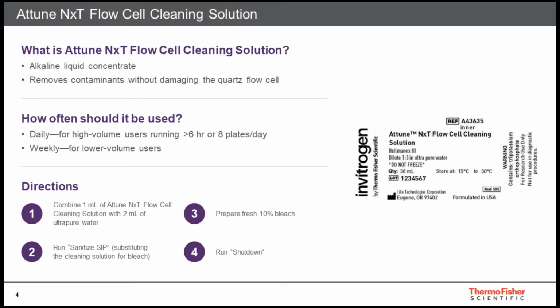Quality of flow cytometry data can be affected by the cleanliness of the flow cell. Attune NxT flow cell cleaning solution is an alkaline solution that does a really good job of cleaning contaminants from the quartz crystal cuvette without damaging it. This solution is recommended to be used during the sip sanitize function just prior to shutdown. The recommended frequency of sip sanitize using Attune NxT flow cell cleaning solution depends on the number of samples being analyzed on the instrument. For high volume users, it's recommended that sip sanitize with this solution be run daily. With low frequency users, running sip sanitize with Attune NxT flow cell cleaning solution at least once a week is recommended.